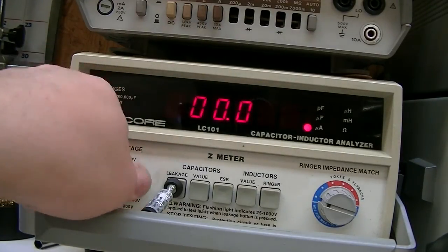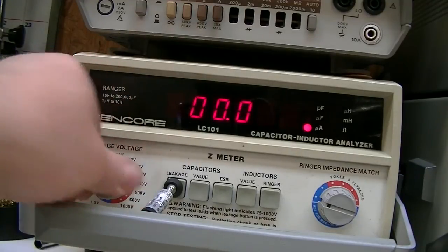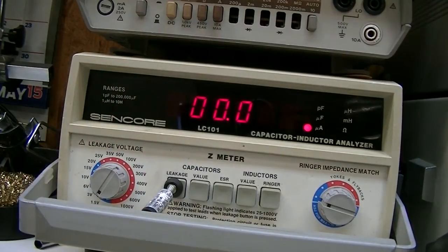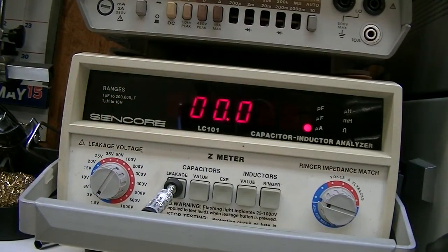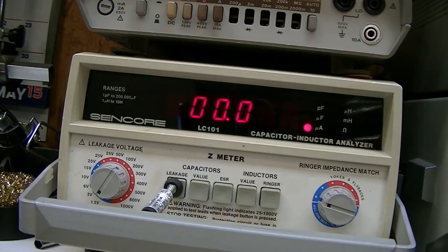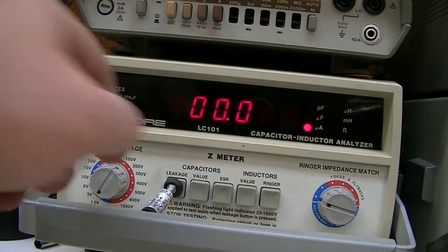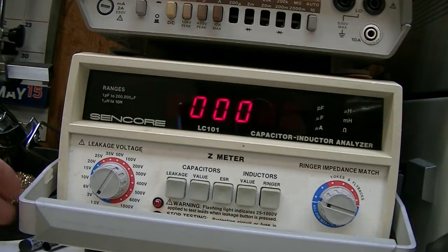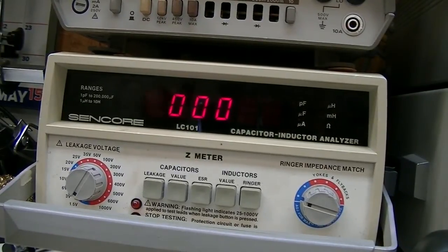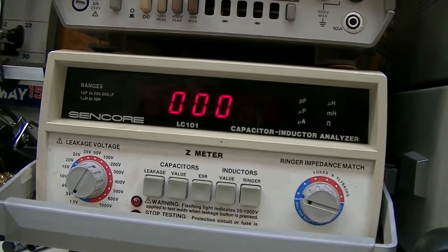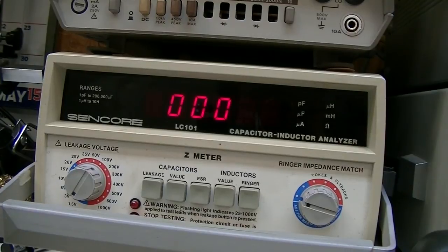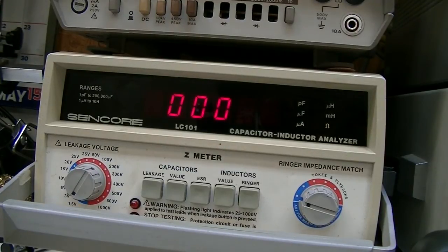It doesn't necessarily always break at the same, or break over at the same voltage. So, that kind of tells me that that IGBT may have been intermittently breaking over. And that might be why this trolley was sometimes working and sometimes not working. That kind of makes sense.